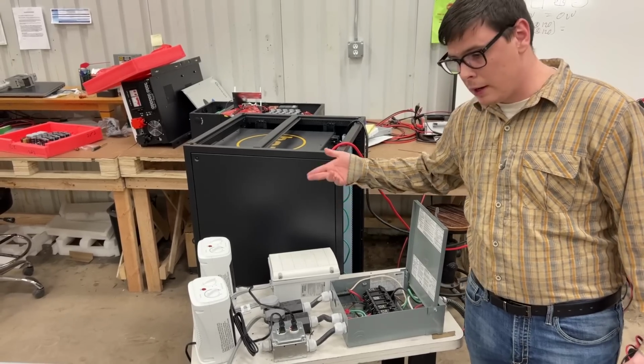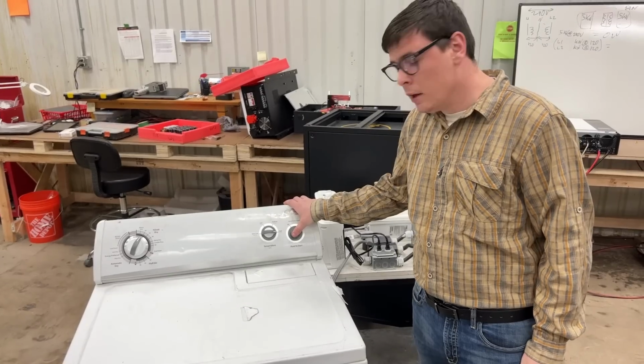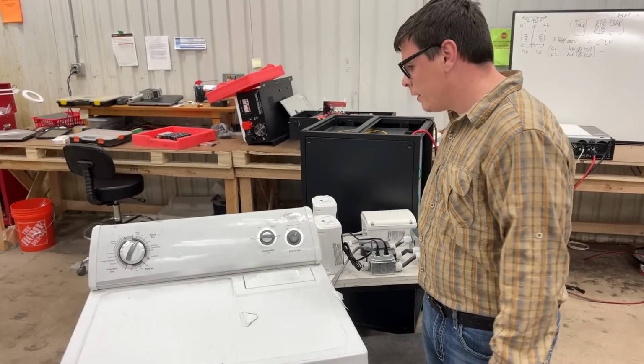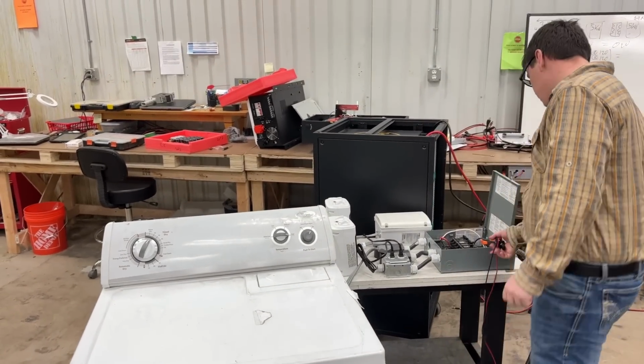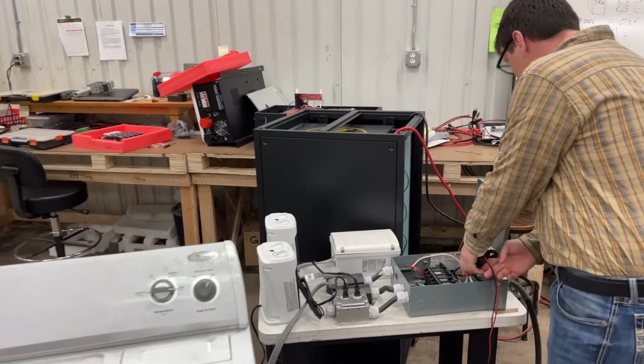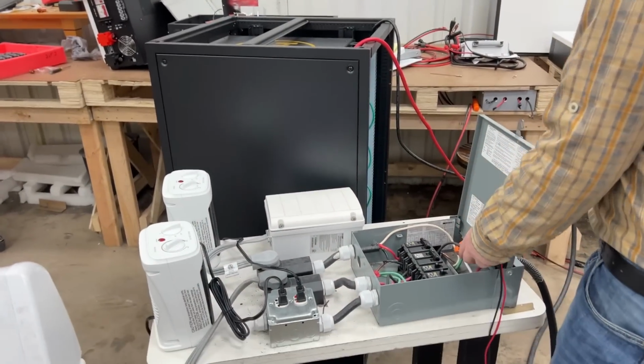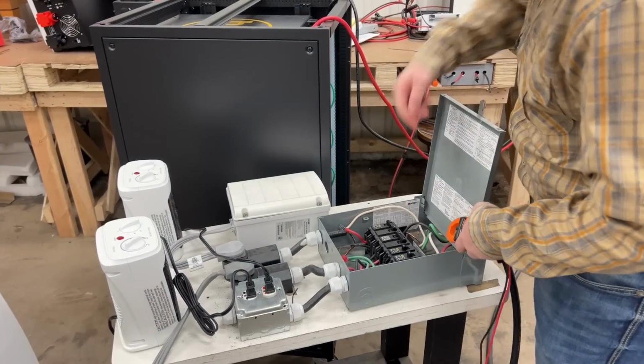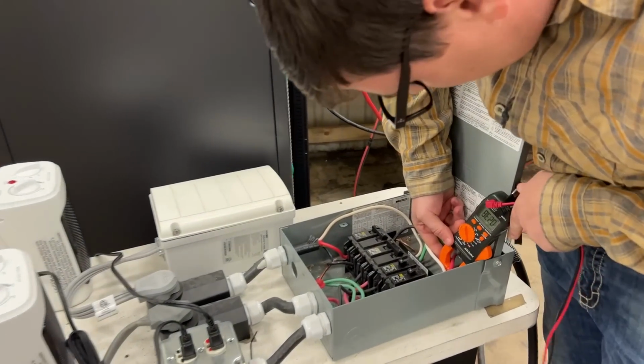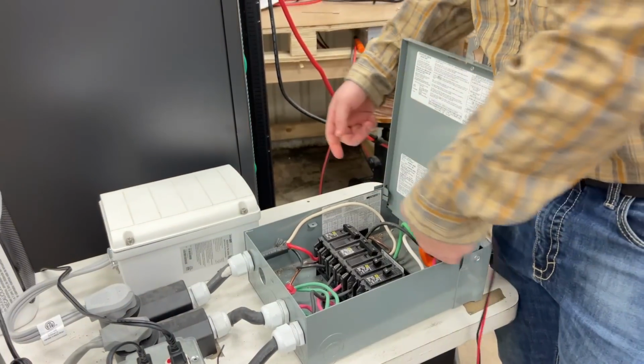We've got what we need right now to run this dryer. So we're going to go ahead and start this thing. I've got, as you can see, 23 amps, actually overrunning the inverter a little bit. 23 amps on line 1. 23.6 amps on line 2.